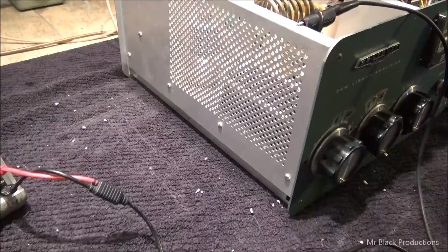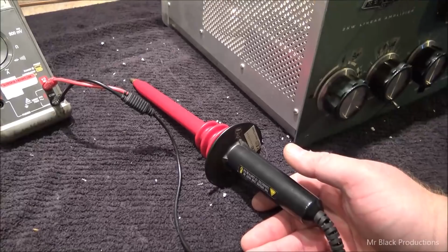Anything that you touch to the inside of the cabinet where there's 3,000 volts present, you're trusting your life in this piece of plastic. Okay? And the only thing that's keeping you safe is its surface area and its inability to conduct electrons, its total length and surface area. Okay? So I haven't stuck this in anything of 10 or 12,000 volts or above. Even though it says it's rated for 40 kV, I would not put this on a 40,000 volt lead. I'd want to have a much more separation distance on 40,000 volts.